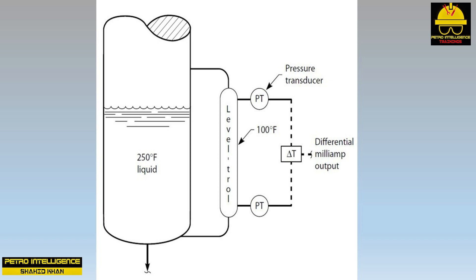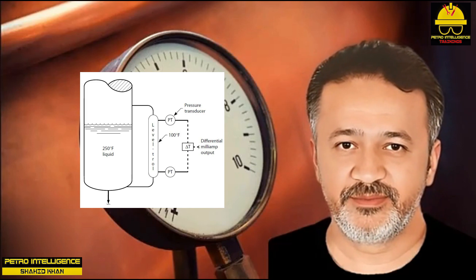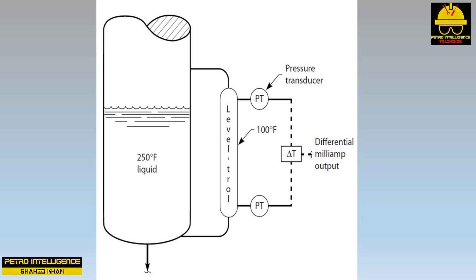The difference between the two pressure transducers is called the milliampere output, which is proportional to the pressure difference between the bottom and top taps. To convert this milliamp signal into a level indication, the instrument technician must assume a specific gravity. The technician should use the specific gravity of the liquid in the process vessel and ignore the specific gravity in the Level-trol. This can be especially confusing when the operator compares the apparently low liquid level in the gauge glass to the higher indicated level on the control panel.